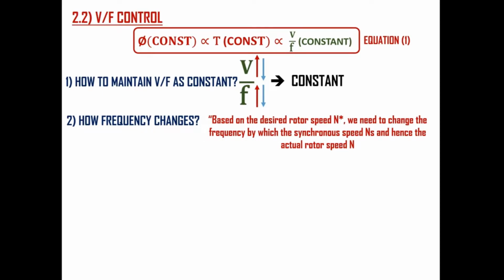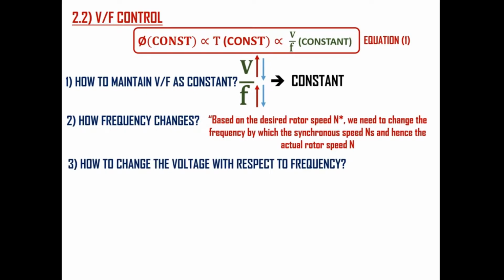Next, we are going to discuss an important point, that is how to change the voltage of induction motor with respect to frequency. As we already discussed, if frequency increases or decreases, the voltage has to be increased or decreased as well. So if we draw a graph between frequency and voltage, it will be almost linear. There are two important points that we have to note in this graph.